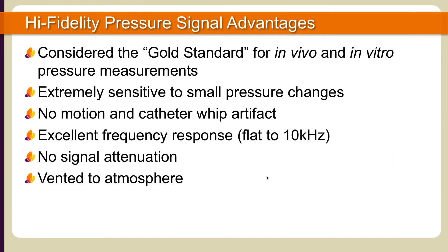A typical cath lab Microcath setup includes the use of a Millar TC510 control unit and cable accessories. It's important to note that the interface cable between the TC510 control unit and cath lab monitor will vary between manufacturers. The TC510 control unit allows for seamless interface to the cath lab's monitoring system and enables users to calibrate and zero-balance the catheter's signal after connection. The Microcath sensor does not require a pre-soak, so setup and calibration can be performed within minutes.